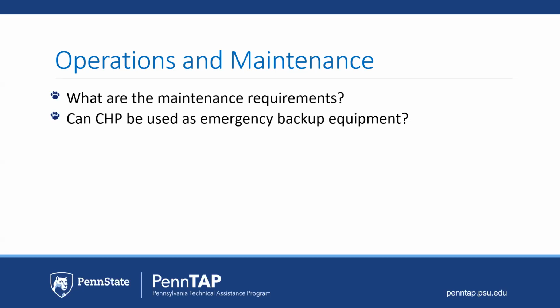Now, can we use CHP? The short answer is yes. The challenge is whether we have the correct electrical infrastructure to do that. When we were building this, we went through about 13 scenarios, asking what happens if the grid goes out of power, or if there's a disruption in fuel. So the short answer is, if you build the infrastructure the right way, the emergency power can serve the emergency load. In a hospital, that's the life safety, critical care, ICU, and emergency load, which is typically about 30% of the building's total load.